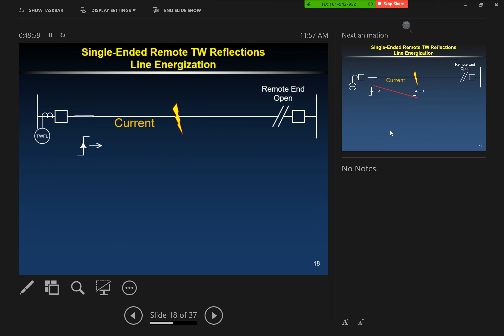Okay, so for lines with complex topologies, let's see what that looks like. I introduced a 1 mile tap in the middle of the line to look at a simple case. For this, I'll split the Bewley lattice diagram into three different sections: what happens in this portion of the line, what happens along the tap, and the second half of the line. So what happens if you have a fault on a complex topology like this? We'll put a fault location down at the remote end and see what happens.